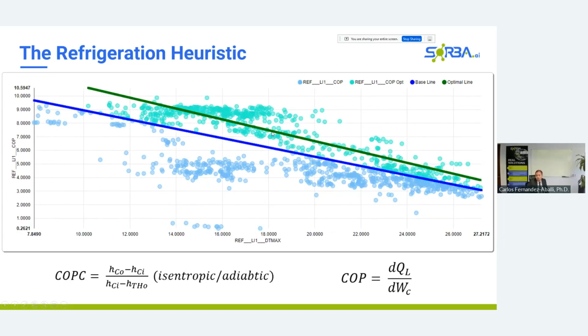Okay, and this is how a typical heuristic works. In this case, we are using the COP, and the blue line is the mean performance of a system. This is real-time data from the system. We remember our bound was the temperature difference between the coldest load and the ambient. So that's what you're paying for. And as you can see, at 16 degrees, your system can perform with a high coefficient of performance over here, or with a low coefficient of performance. And that spread happens throughout different temperature differences.